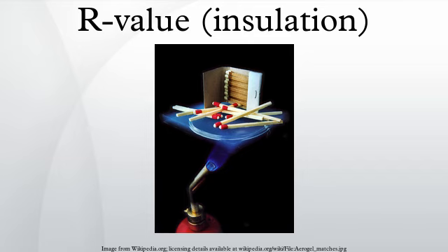With a good radiant barrier in place, most heat flow is by convection, which depends on many factors other than the radiant barrier itself. Although radiant barriers have high reflectivity over a range of electromagnetic spectra, their thermal advantages are mainly related to their emissivity in the infrared range. Emissivity values are the appropriate metric for radiant barriers. Their effectiveness when employed to resist heat gain in limited applications is established, even though an R value does not adequately describe them.